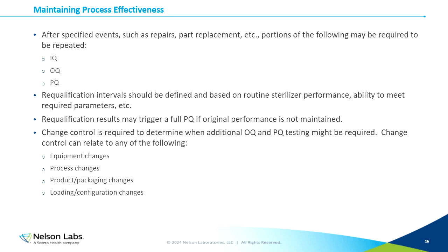Anytime we make a change, we need to make sure that we're following change control. Change control is required to determine when additional testing might be required. Change control could relate to equipment changes. It could relate to process changes. It could relate to product or packaging changes. And it could relate to loading or configuration changes or even other items.